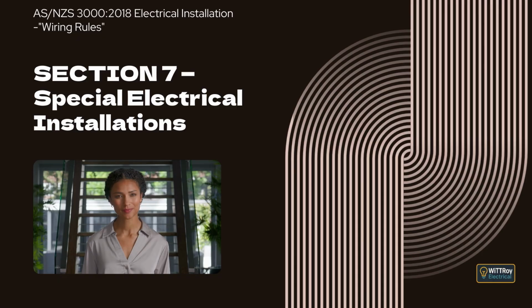Clause 7.2.4.3 Mechanical Protection. This clause explains that switches and control equipment forming part of a safety service installation must be adequately protected if their location or conditions of use mean they could be subject to mechanical damage. The intent is to make sure the switch remains operable during an emergency.